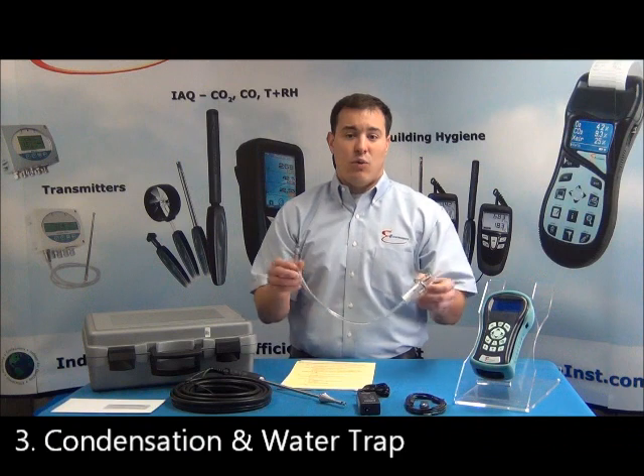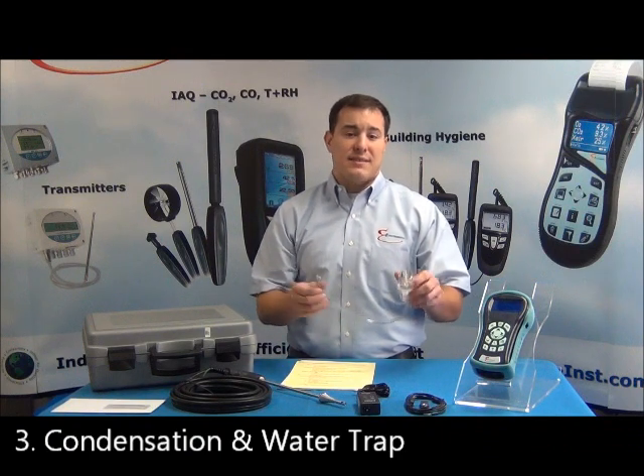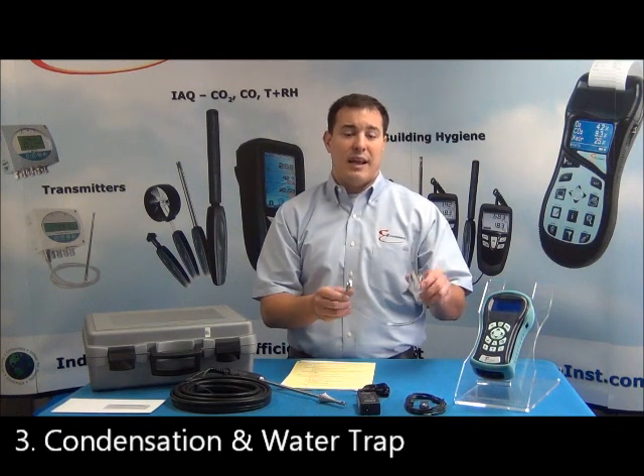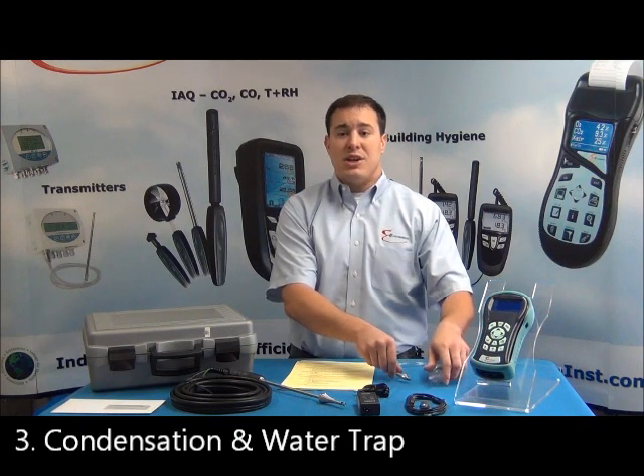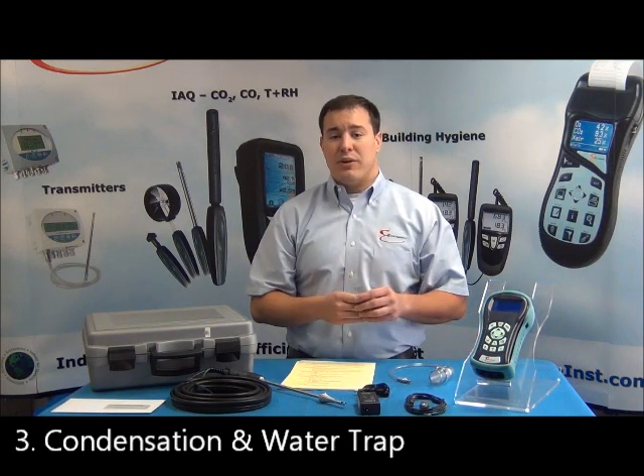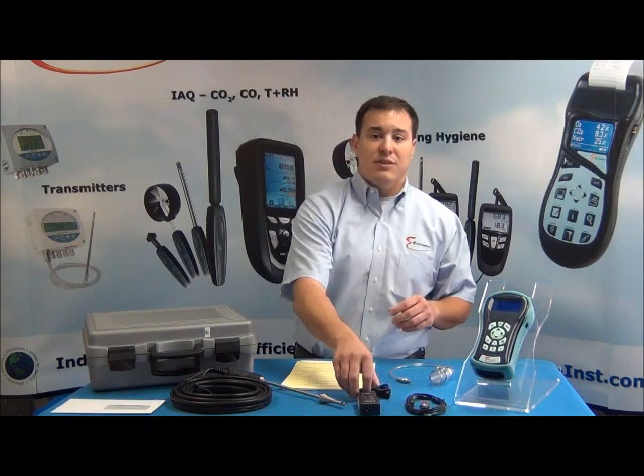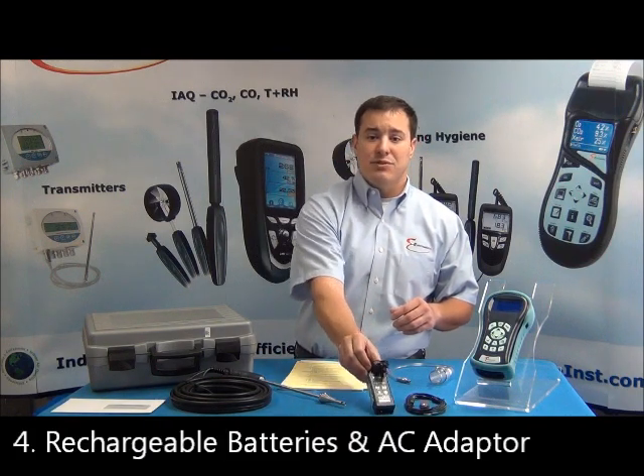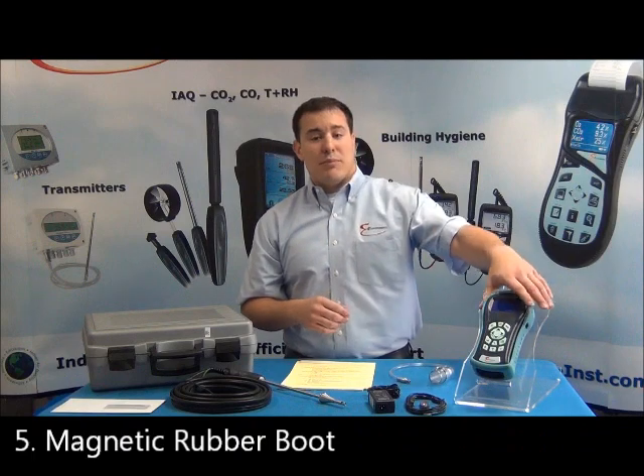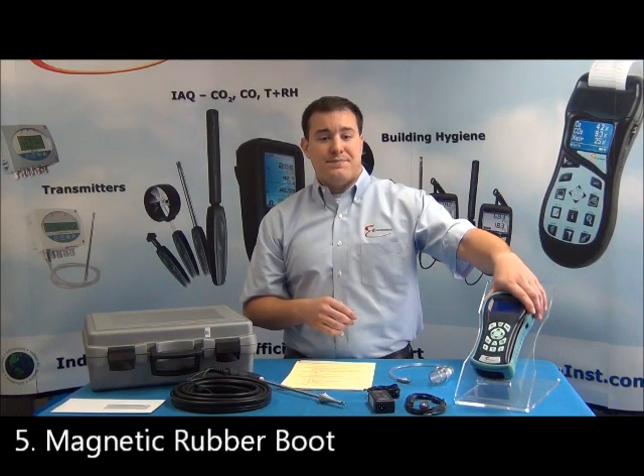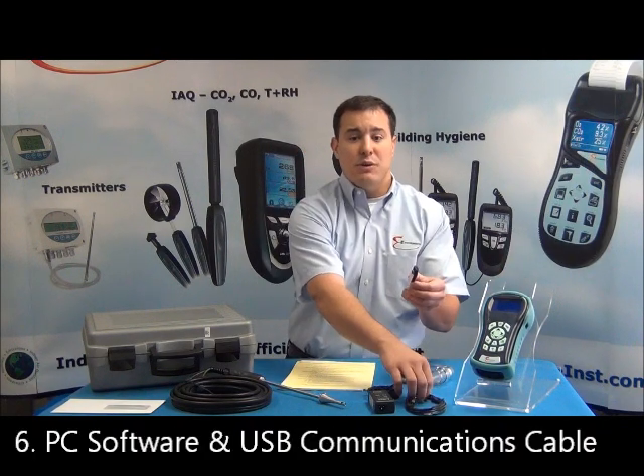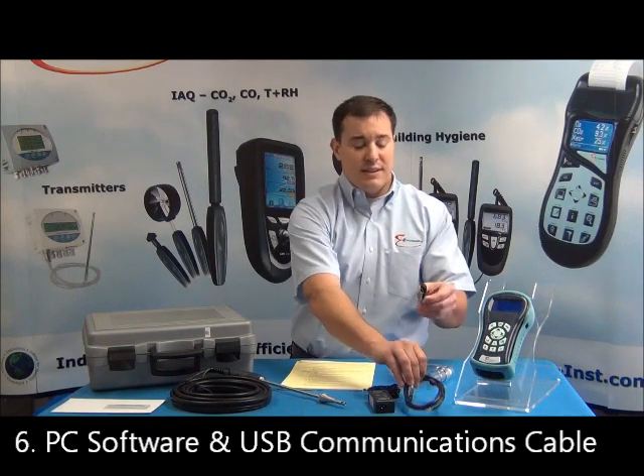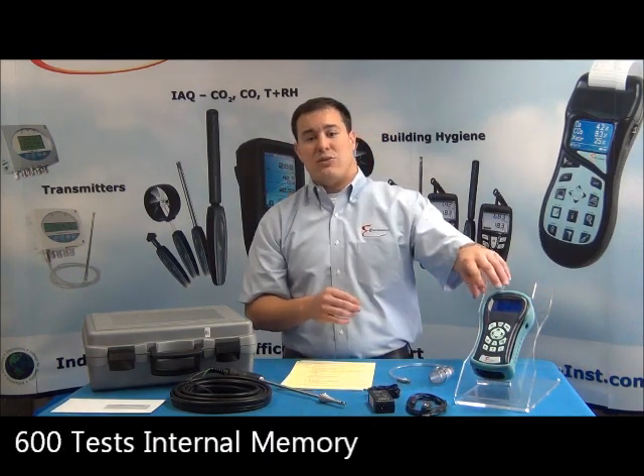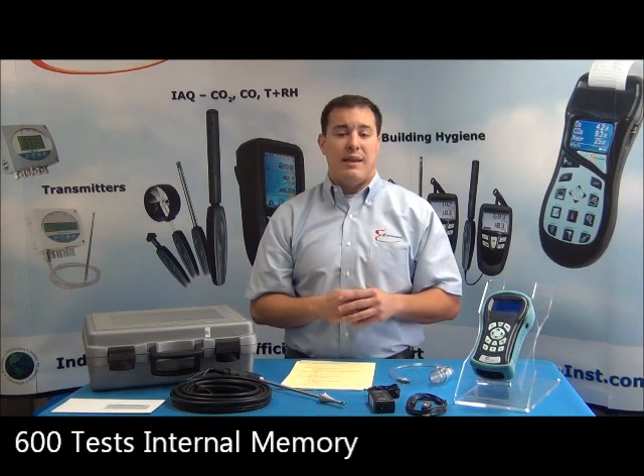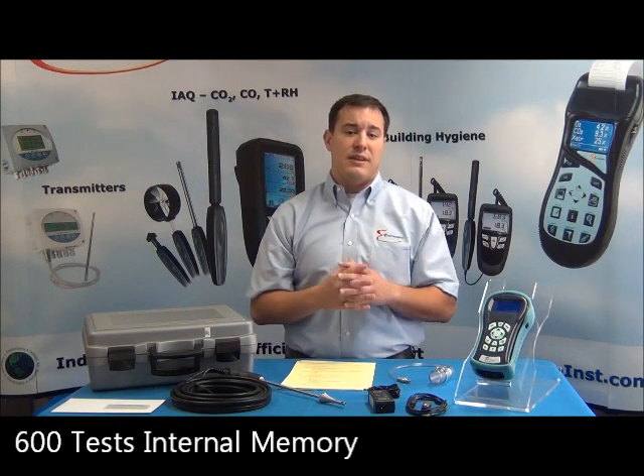The condensation and water trap is included. Watch our pre-test setup and maintenance videos for more information on how to easily empty the water trap, change the filter, and take care of this very important assembly. The analyzer comes standard with your rechargeable batteries, and AC adapter is also included. The magnetic rubber boot for hands-free operation. The PC software and USB communications cable. The unit itself can hold up to 600 tests in the internal memory, and each test can be easily named or labeled in the field and then later easily downloadable to your laptop or PC.